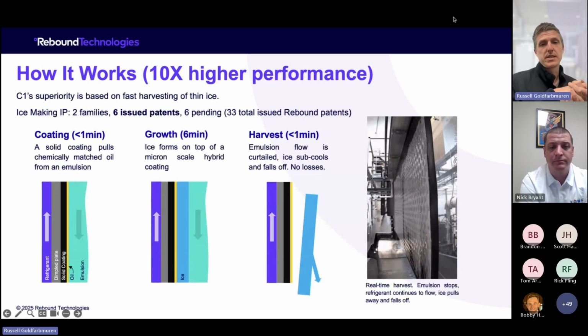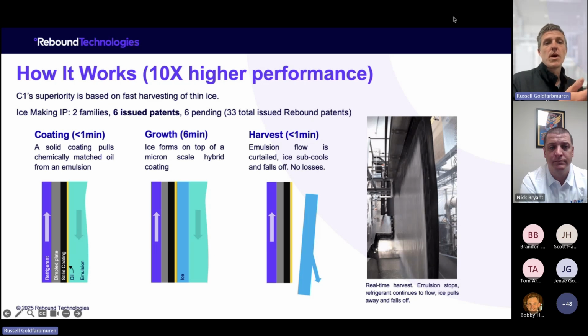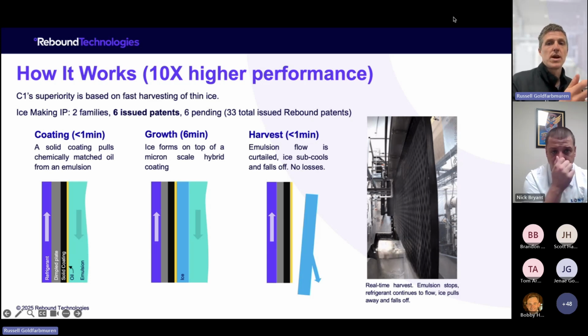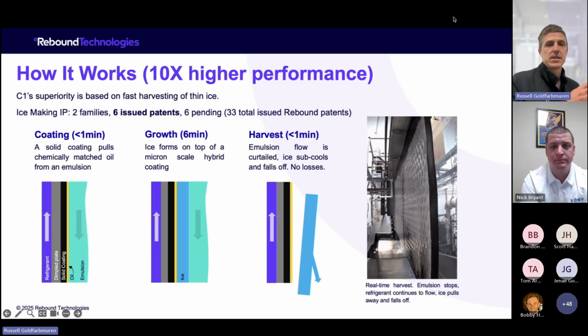what is actually in our box? What have we done that's different? Why did it take us 13 years to make this technology? So what we realized right off the bat when we started is that ice storage needs a specific solution. We can't just use the ice making technologies of the past to solve the problems of the future. And so we developed an ice maker from scratch, specifically geared towards thermal energy storage. We do really advanced surface chemistry that basically amounts to we grow ice on top of a liquid layer, on top of an oil, and we harvest it with subcooling. We harvest in about 20 seconds, and we grow very thin, very efficient quarter-inch thick ice. Overall, this gives us 10x more ice making for the same surface area as a traditional system.